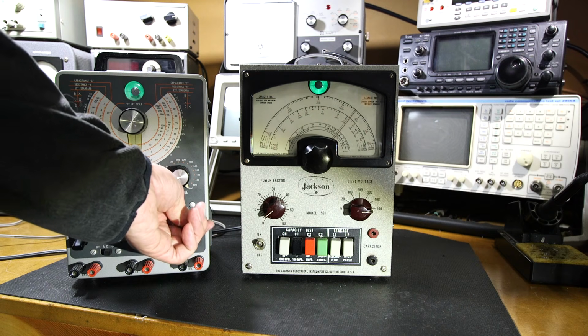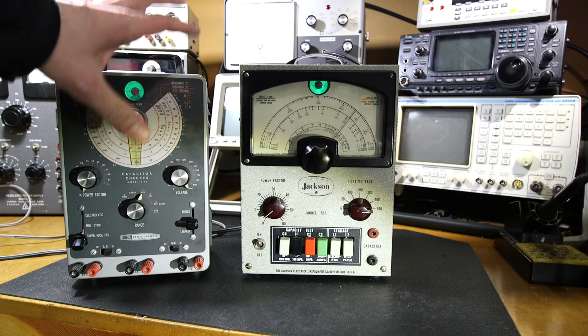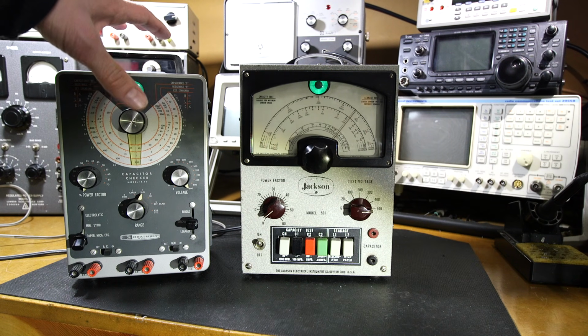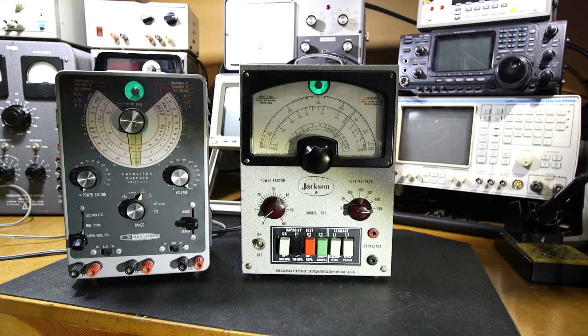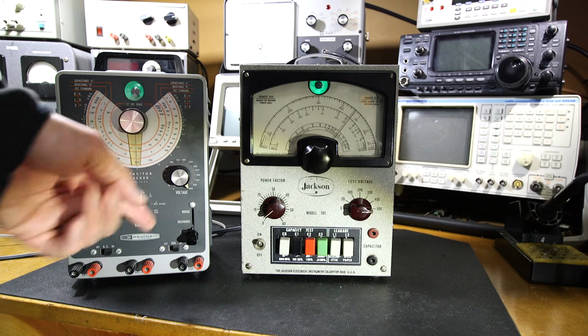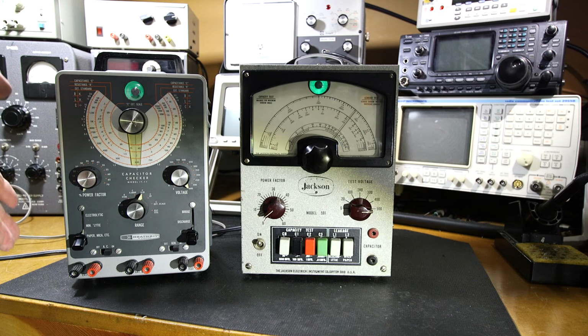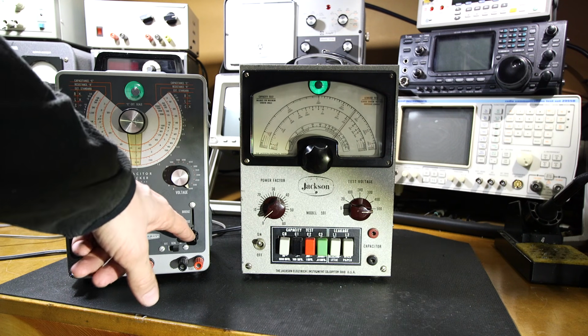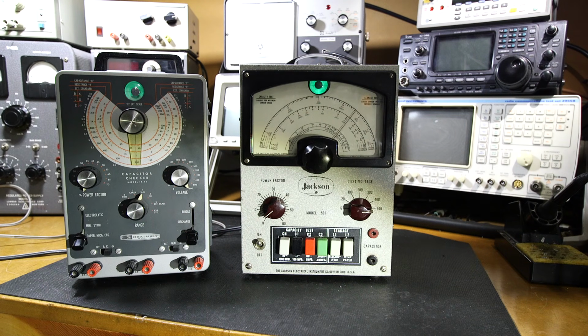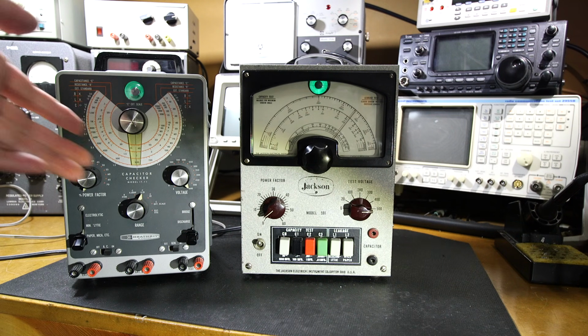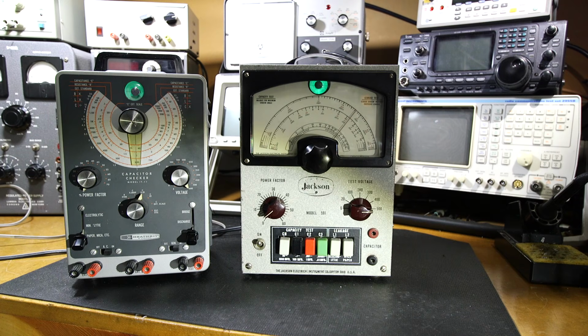When you're using a device like this, you have to be extremely careful. If you own one of these things and you're not familiar with it, read the manual, because it will lock in the leakage position. If you shut it off, leave it, and come back the next day forgetting it's still in the leakage position with probes sitting on your bench, and you turn on the master switch, those probes would be live — that could be a very dangerous situation.